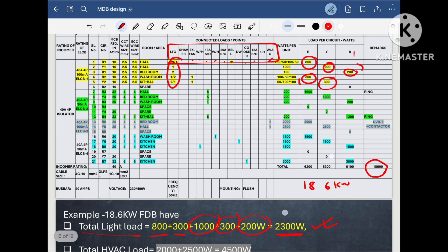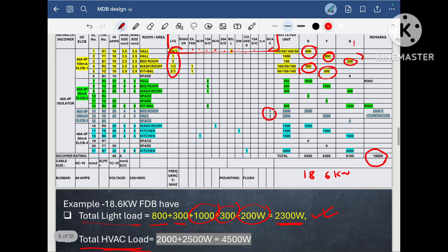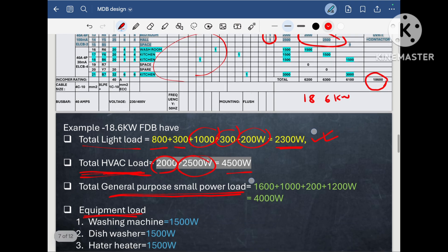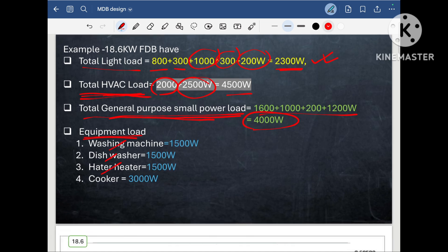In the same way, I tabulated the HVAC load. The window AC loads are 2000 Watt and 2500 Watt, so the total HVAC load on this DB is 4500 Watt. Similarly, I calculated the general purpose socket load, which comes to 4000 Watt. And for equipment — washing machine, dishwasher, water heater, and cooker — the loads are 1500 Watt, 1500 Watt, 1500 Watt, and 3000 Watt respectively.